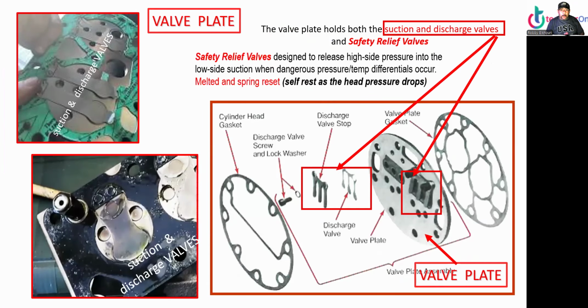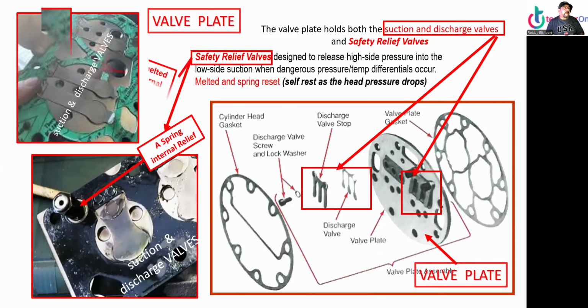Safety relief valve is designed to release high side pressure into low side suction when a dangerous pressure or temperature differential occurs. Melted and spring reset. Those are the two we have. Self reset as head pressure drops. The spring is self reset. The melted melts. So this is the spring here. You can see it there. I'll cover it next slide. And this one is the melted. This one got heated and melted off.